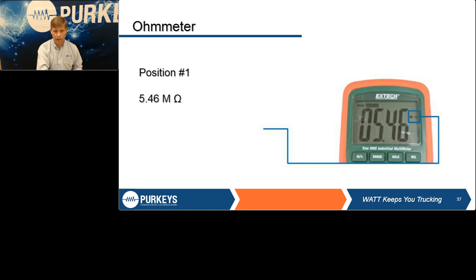Again, the spec called out in the service bulletin says the sensor should be at least 6K. Well, first off, you have to know how much 6K is. Anytime you get a K, it's going to tell you 1,000. So the spec is looking for at least a 6,000 ohm reading. If you look at what our meter is displaying, a lot of times people say it's 5.46, it's less than 6K, it's good.